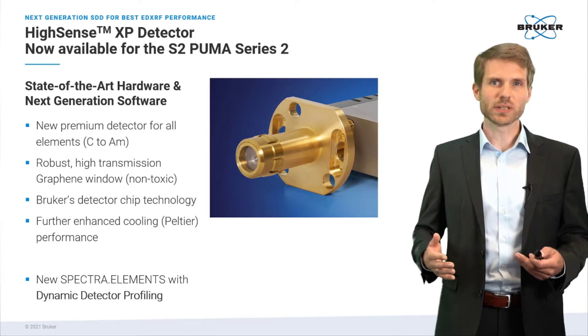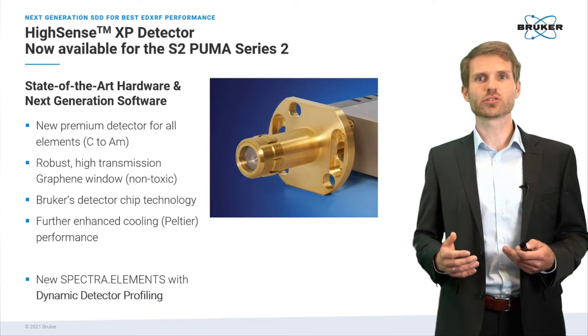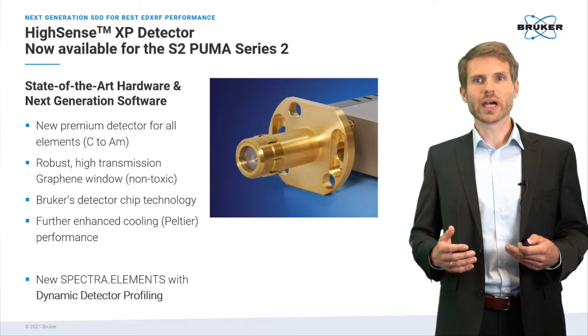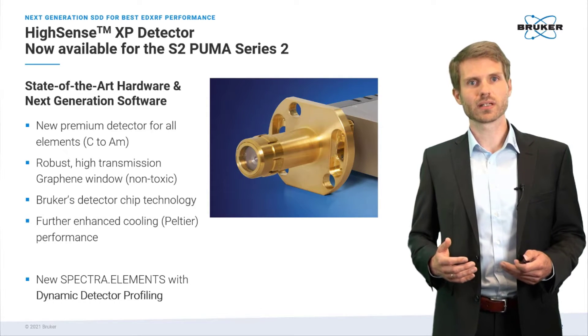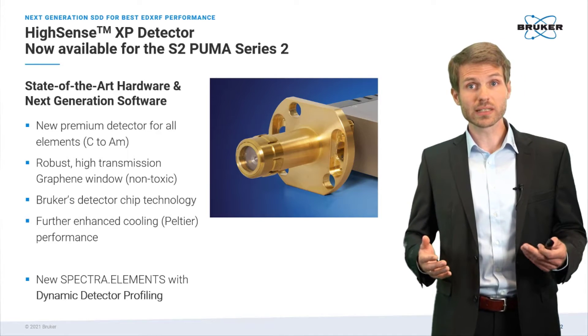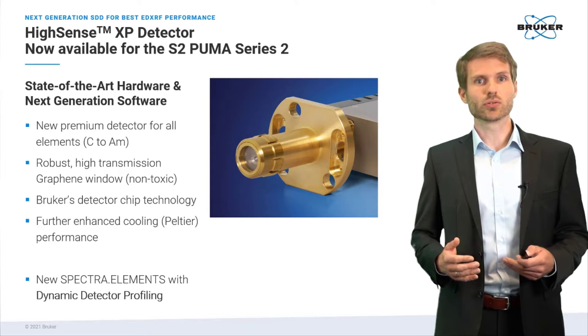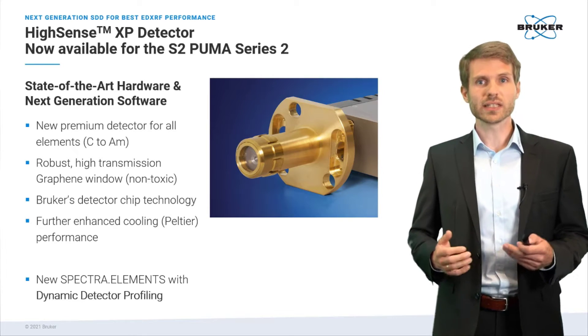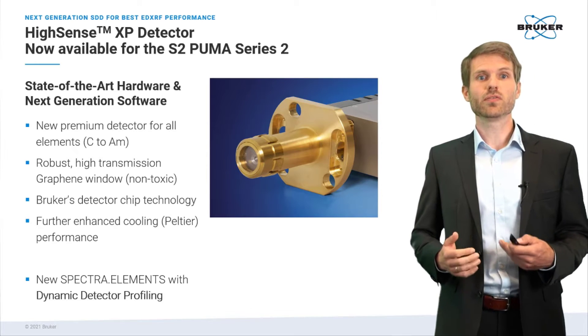The HighSense XP is equipped with an ultra-robust high transmission graphene window and makes use of Bruker's own chip technology. Like all the detectors of the HighSense class, the XP does not require liquid nitrogen and uses electric Peltier cooling. The cooling setup has even been enhanced with the XP for even better performance.